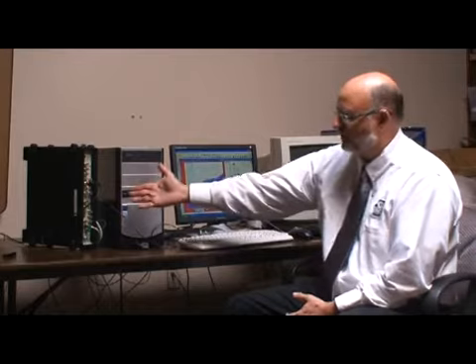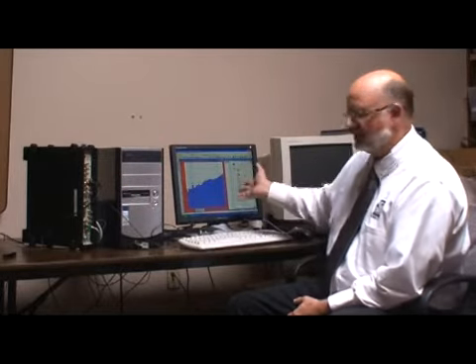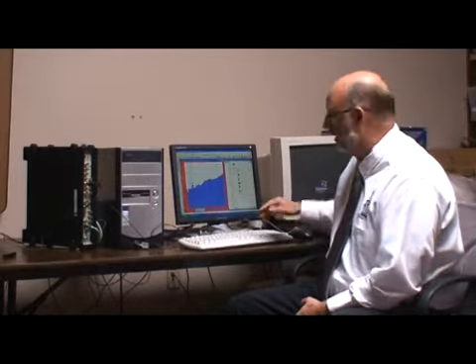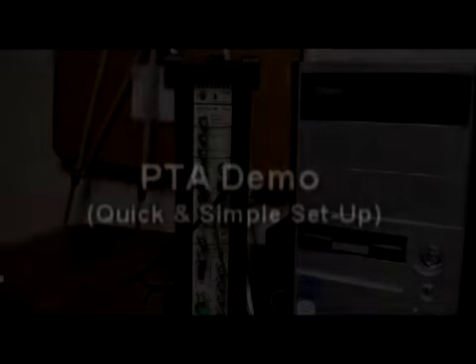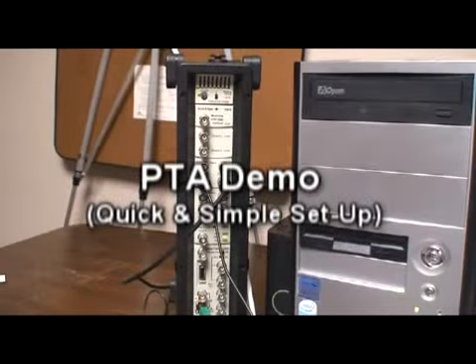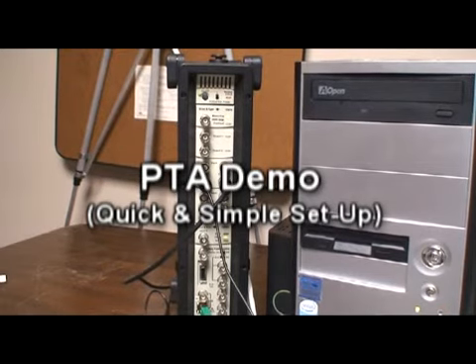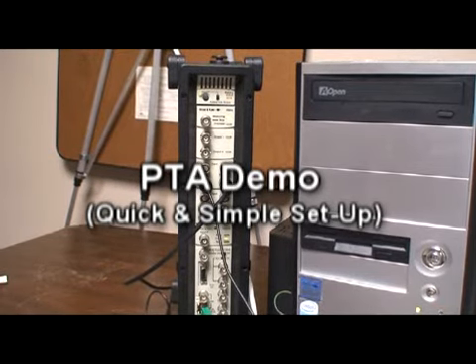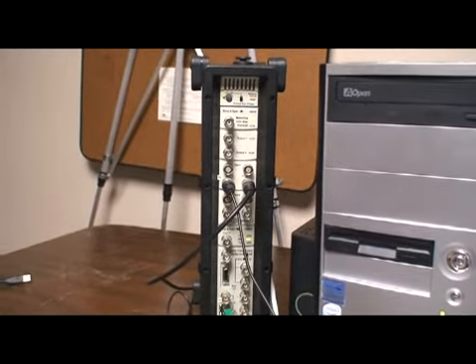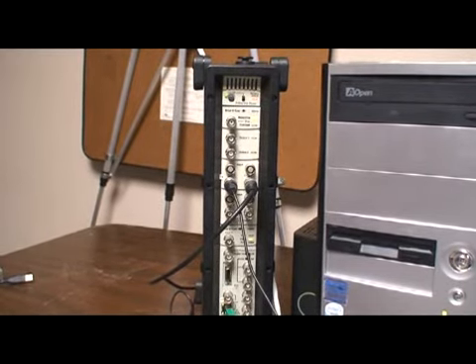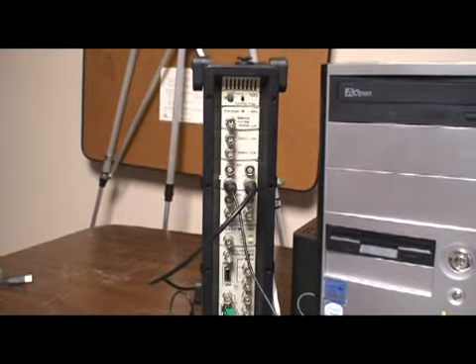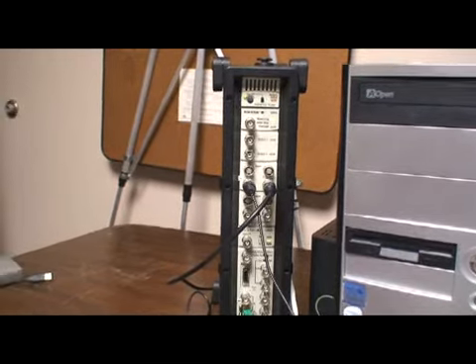Here we have our PULSE system, PULSE front end, and the computer that has PULSE LabShop on it and also the PTA software. What I will do now is demonstrate a simple, quick setup of doing pass-fail on an autospectrum. We'll be using just a signal generator to drive the data, but it'll be simple. We have two channels plugged into our PULSE front end.